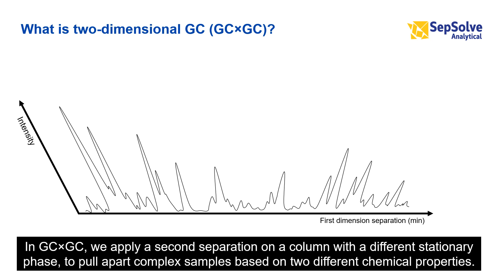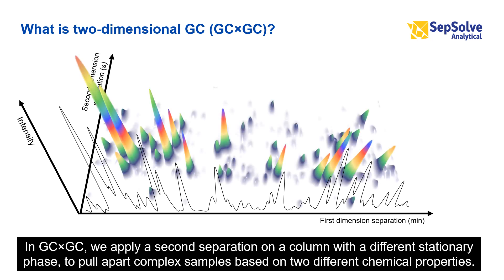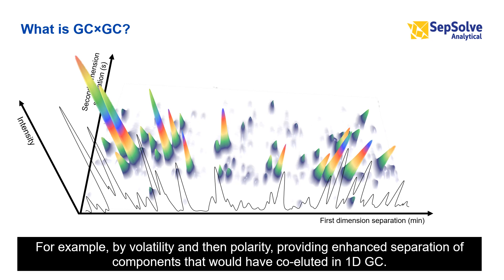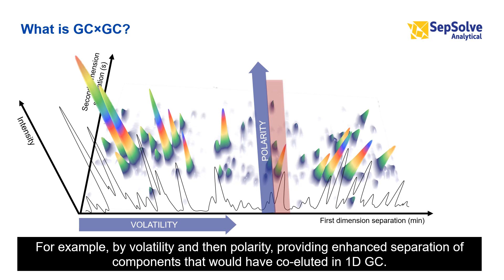In GC×GC, we apply a second separation on a column with a different stationary phase, to pull apart complex samples based on two different chemical properties — for example, by volatility and then polarity — providing enhanced separation of components that would have co-eluted in 1D-GC.